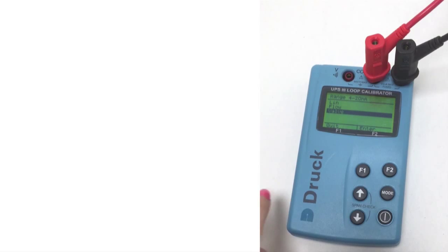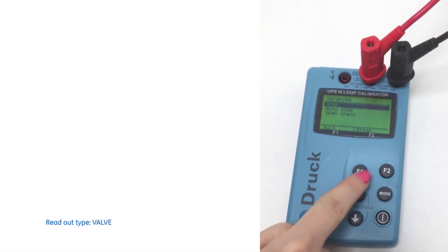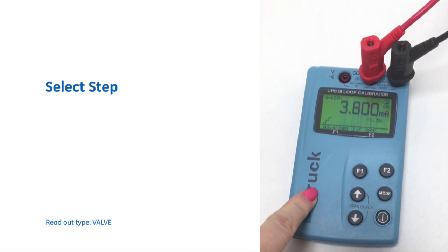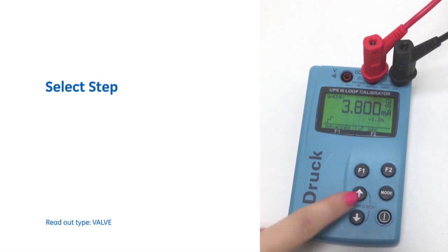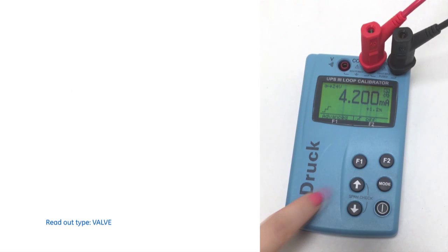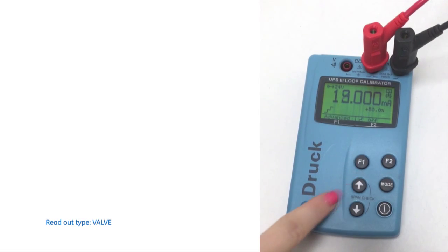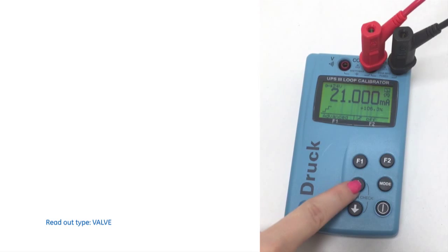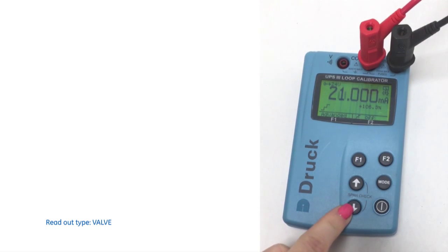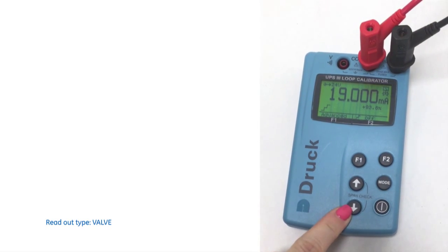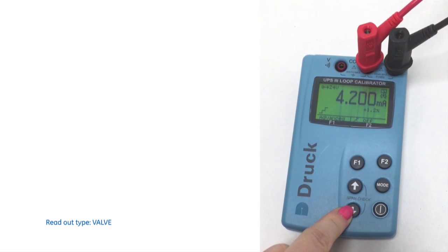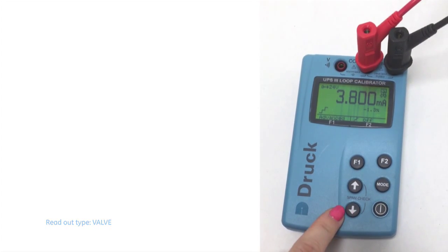So the last thing I want to show you is just the valve option. So if we select valve, we're just going to select step. This enables you to go from 3.8 to 4, 4.2, 12, 19, 20 and 21. That just gives you that extra bit at each end just to see when a valve may be opening and when that's actually fully opened there.